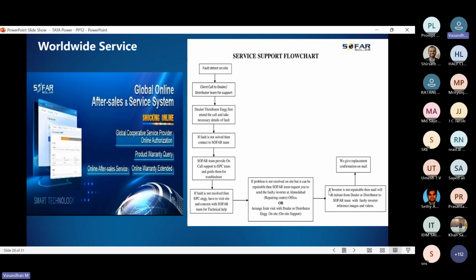So this is the flow chart. Once, for example, we cannot solve the issue, after checking we need to change any spare part like display board, communication board, or control board based on the fault code. We check on our end, and we can solve the issue 80% online itself. The remaining 20% only needs offline support, for example spare changes - we get the spare from our Ahmedabad office and send it to the customer place. If the inverter itself has failed, we cannot repair it, so we replace the inverter. This is based on the fault code only, and we finalize the issue accordingly. These are the service support flowchart steps we follow.